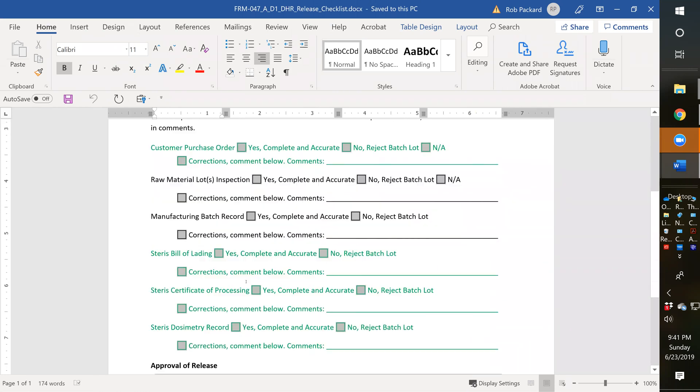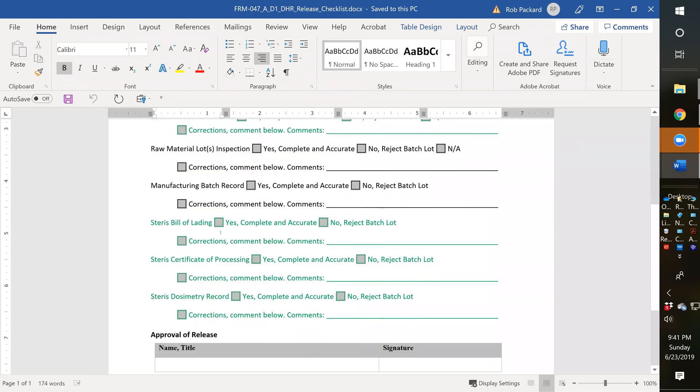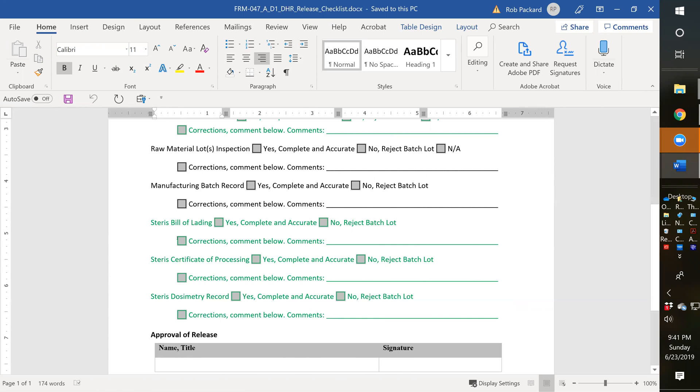For these three items here, they're related to a gamma sterilization process. If you don't have gamma sterilization, you're going to either change or delete this. You could list each of the requirements for all sterilization processes and write NA next to them. But I think the better way is to have one for each product specific to what should be in there, so the person filling out the checklist doesn't have to look things up. They can go right off the checklist and say yes or no, rather than not applicable.